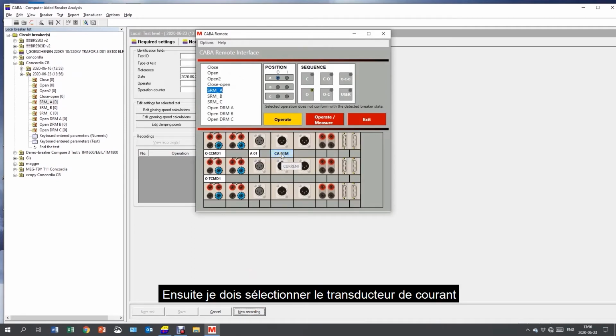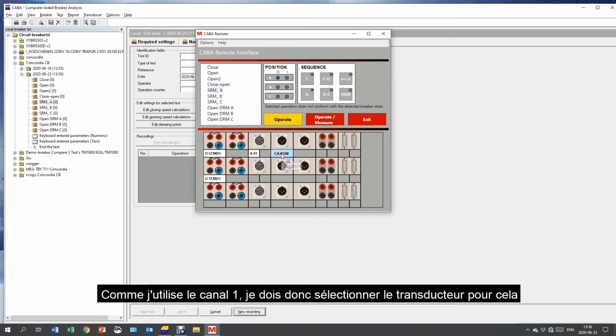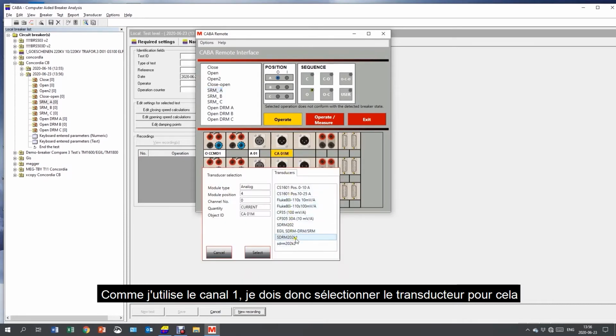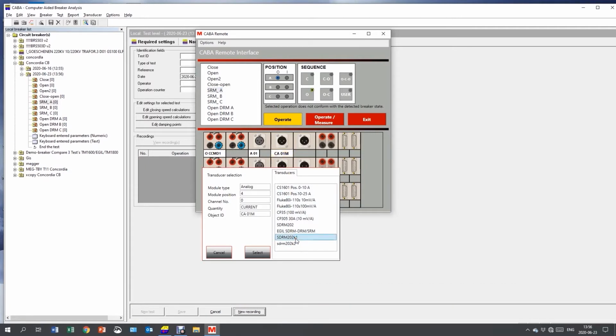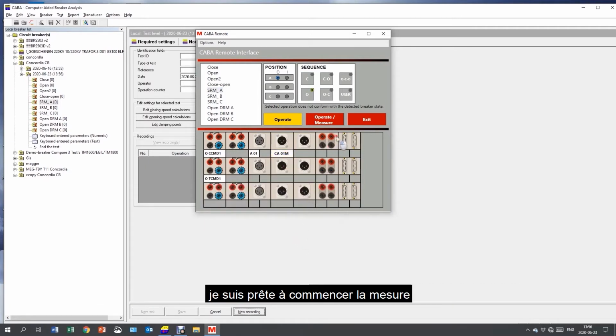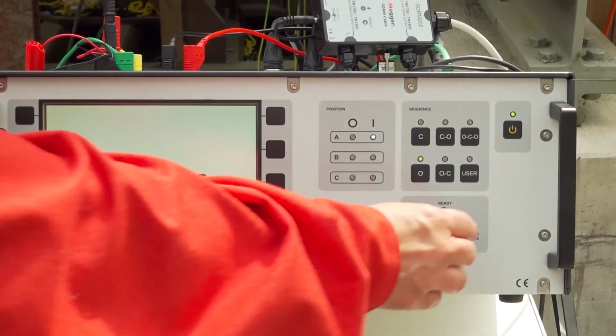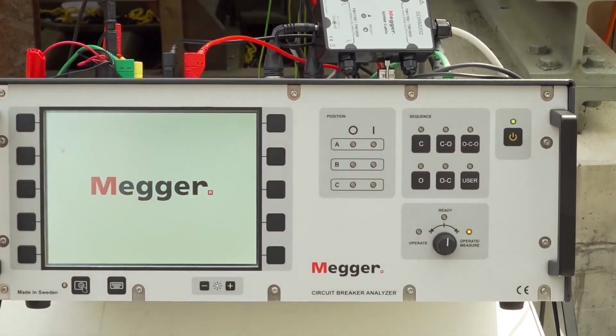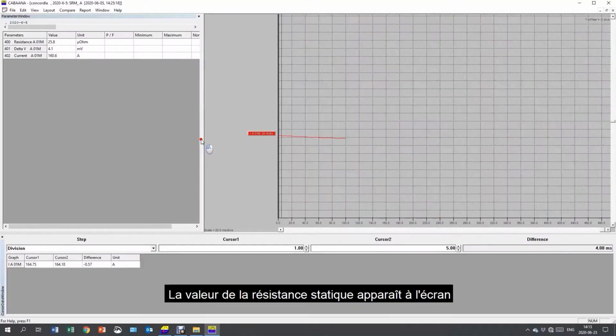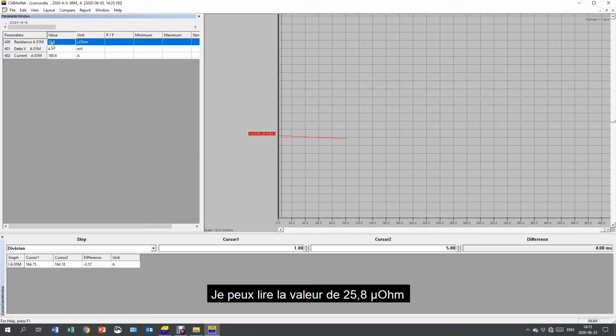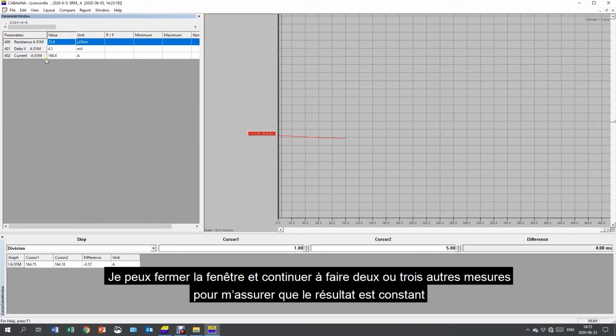And I need to select the current transducer. And I'm using channel 1, so I need to select transducer for that. And now I'm ready to start the measurement. The static resistance value occurs on the screen. I can read out the value 25.8 microohms. I can close the window and continue to do 2 to 3 more measurements to see that the result is constant.